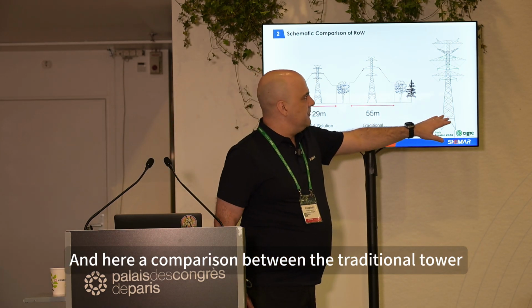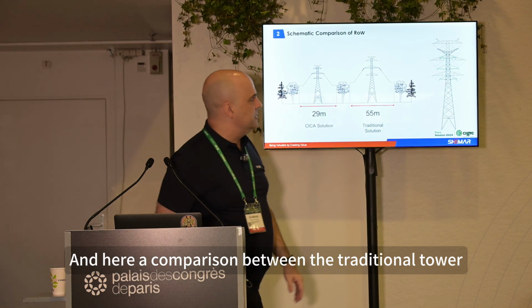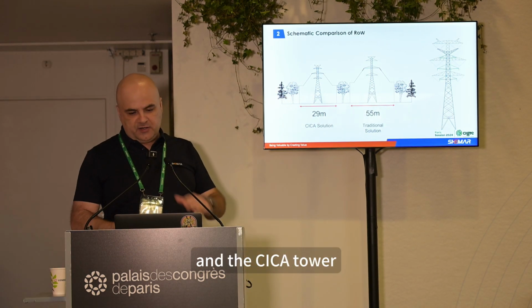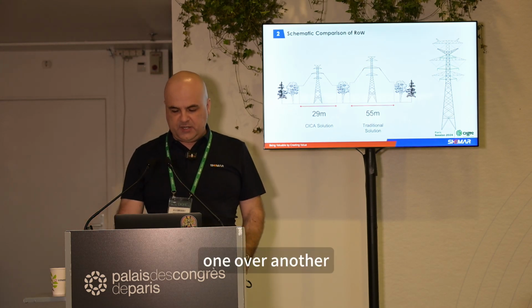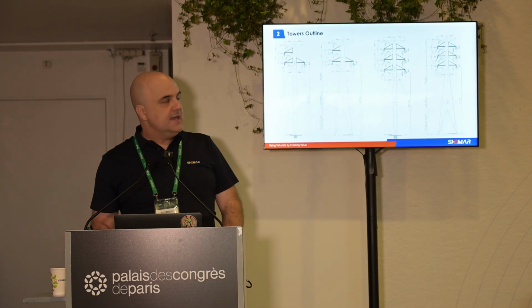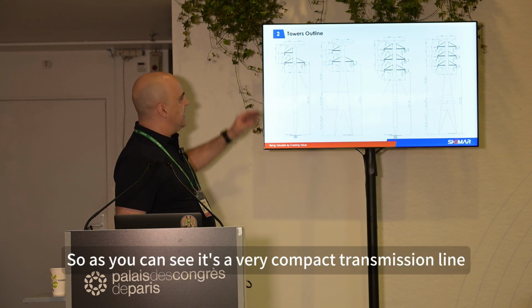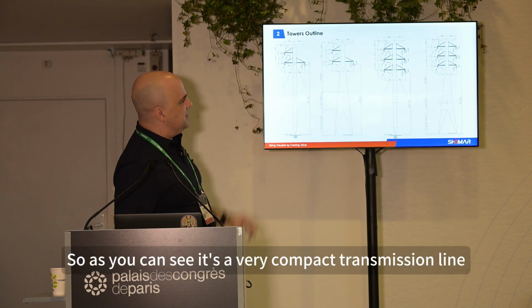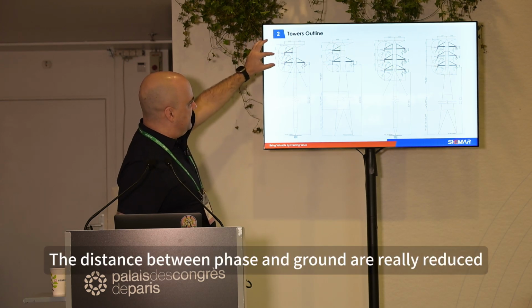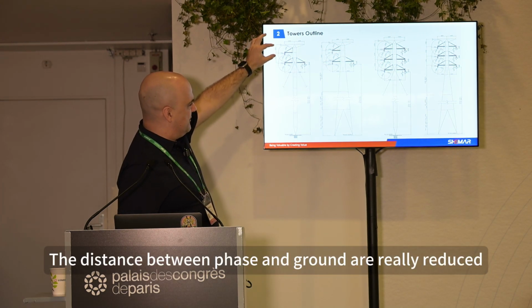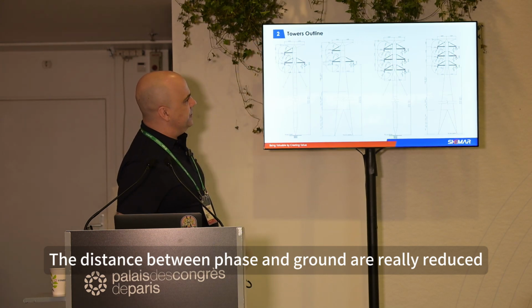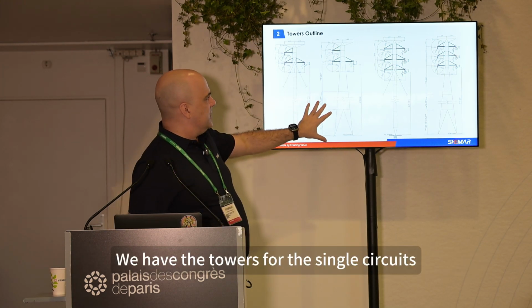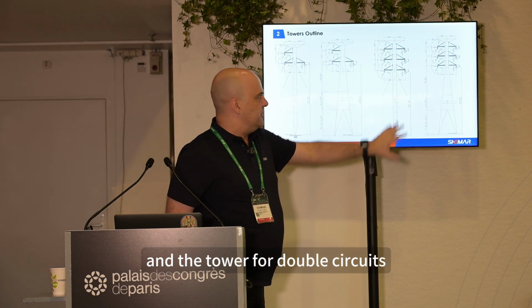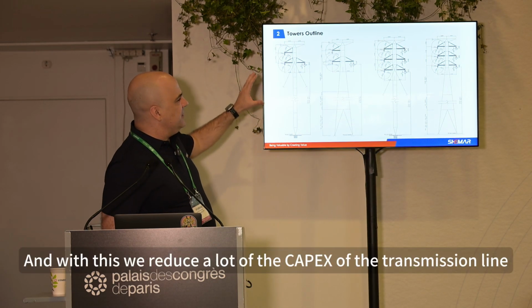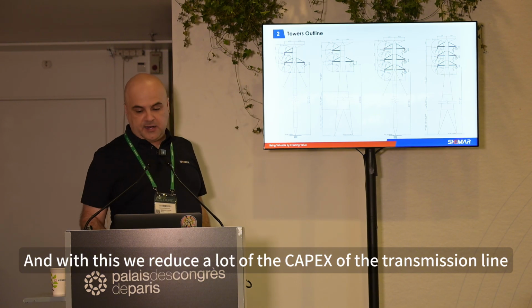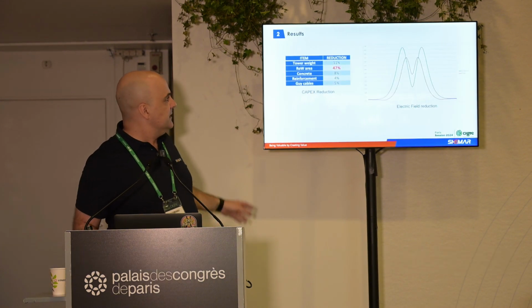Here's a comparison between the traditional tower and the CICA tower, one over another, and the tower outlines. As you can see, it's a very compact transmission line -- the distances between phases and between phase and ground are really reduced. We have towers for single circuits and towers for double circuits, and with this we reduce a lot the capex of the transmission line.